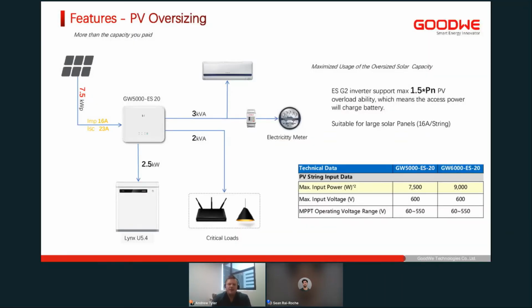We spoke about the PV oversizing earlier. Here's the visual representation of this. We've used the 5 kilowatts in this example again. We've got 7.5 kilowatts of PV connected to the inverter, and you'll see that all of that 7.5 kilowatts can be utilized at any given point. This is not something that's common in our industry with hybrid inverters. Typically, you have an overhead of 20 or 30%, but that's really for efficiency losses and over paneling.